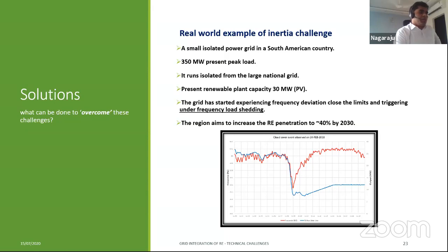So they came up with a problem, saying that at the moment they have around 30 megawatts of PV in the system. On some days when the PV is running at full capacity and the demand is quite low, all the conventional plants, which mostly run on gas turbines and diesel generators, they take out those and run the system mainly on these PV plants. And there are two 15 megawatt PV plants, and the remaining are on gas turbines.